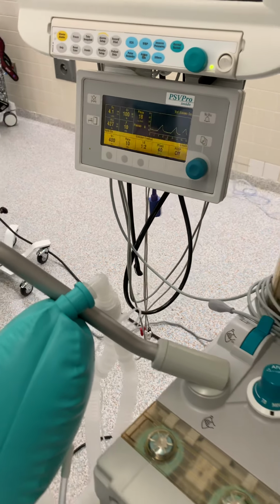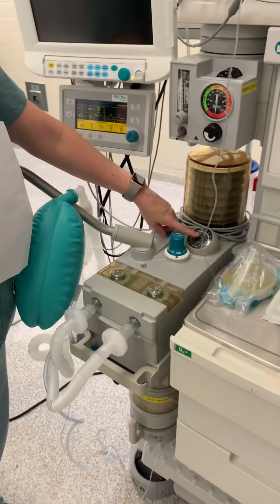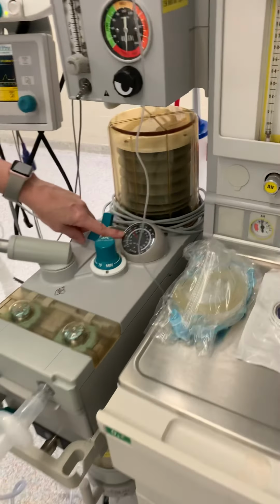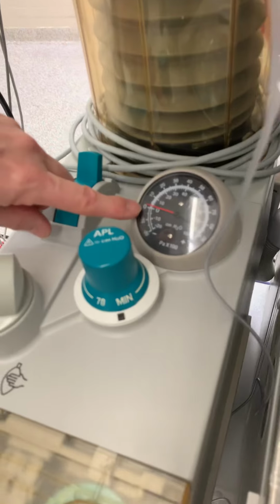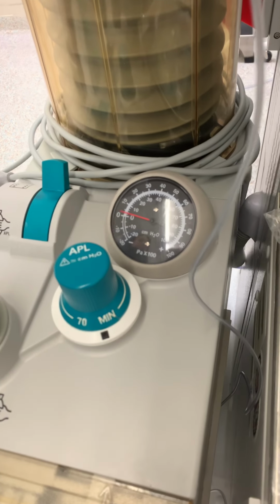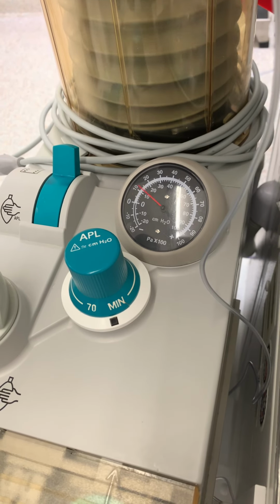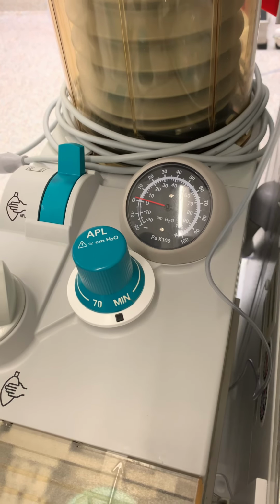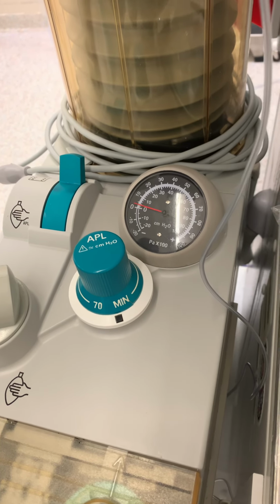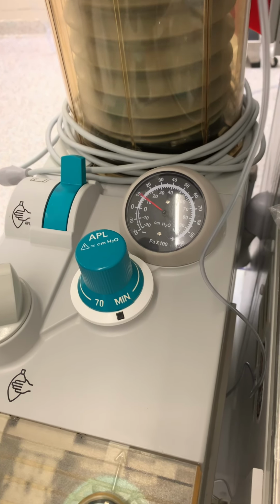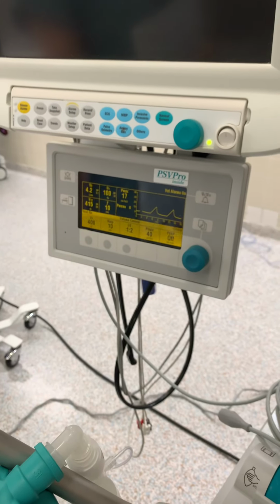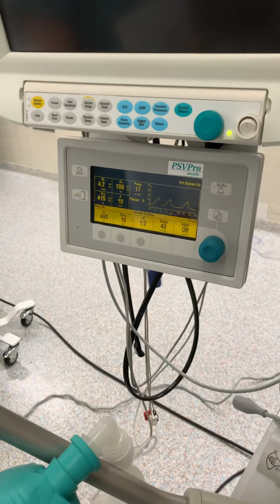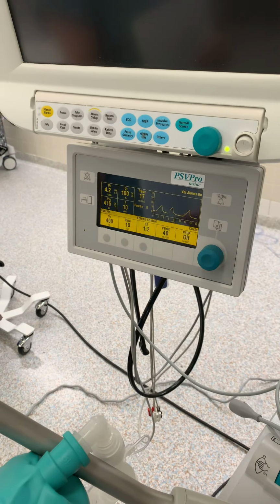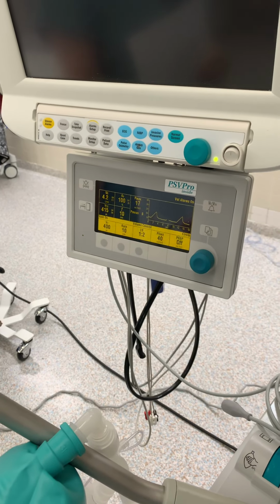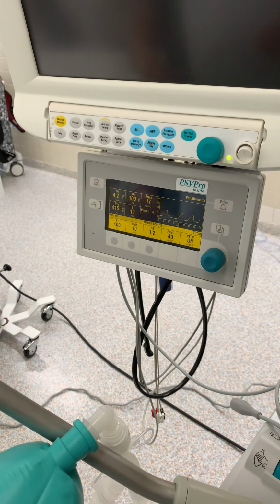And while we're waiting and looking at that, we want to also be looking at the manometer and making sure that after each breath it is returning to baseline. And it is, so that it's not experiencing a sustained pressure. So as you can see, we've essentially come back down to baseline, even with an increase in your oxygen flow, which is what you wanted to see. So that is the end of the ventilator check.